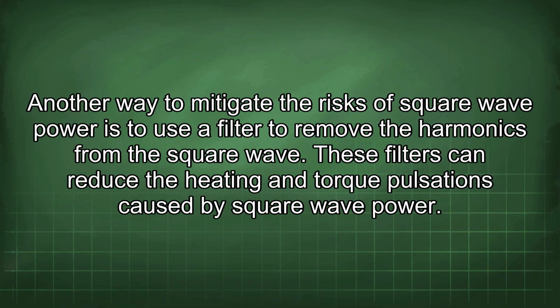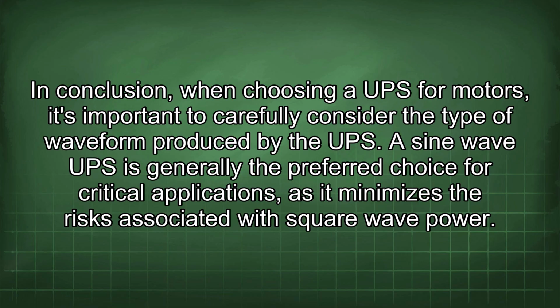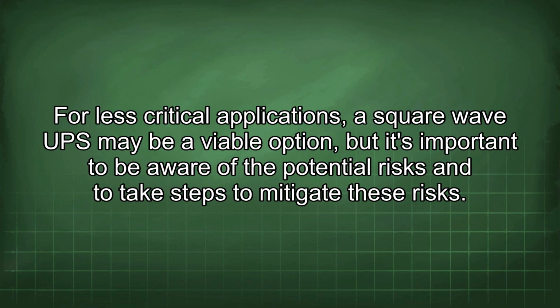Another way to mitigate the risks of square wave power is to use a filter to remove the harmonics from the square wave. These filters can reduce the heating and torque pulsations caused by square wave power. In conclusion, when choosing a UPS for motors, it's important to carefully consider the type of waveform produced by the UPS. A sine wave UPS is generally the preferred choice for critical applications, as it minimizes the risks associated with square wave power. For less critical applications, a square wave UPS may be a viable option, but it's important to be aware of the potential risks and to take steps to mitigate these risks.